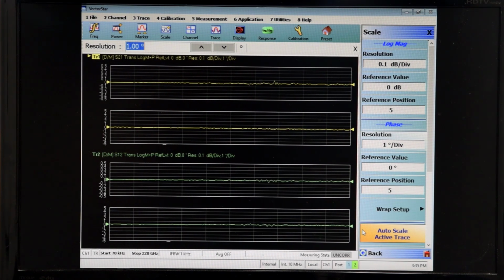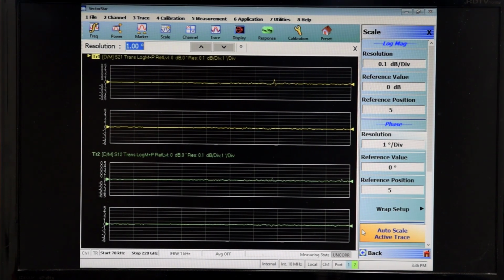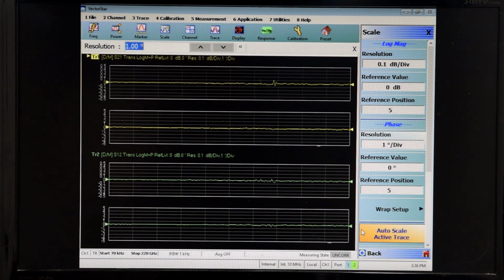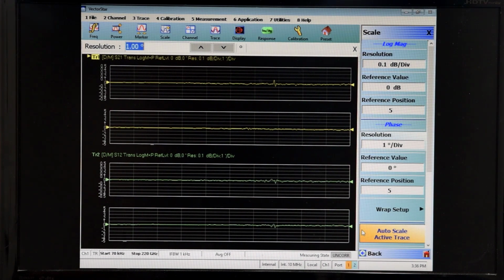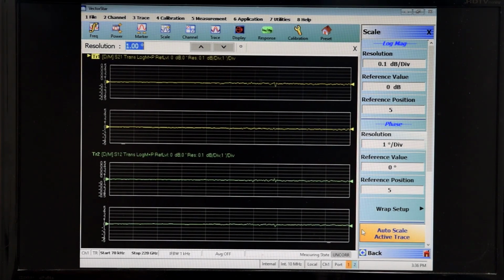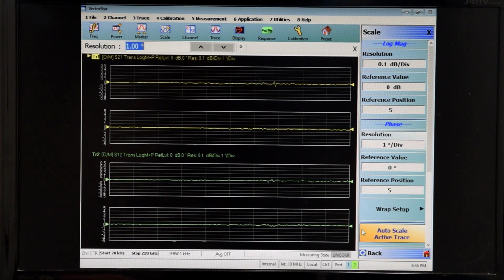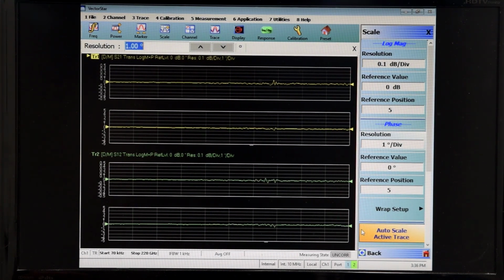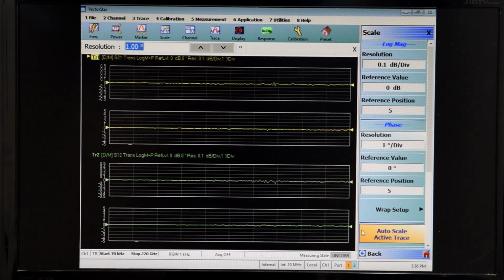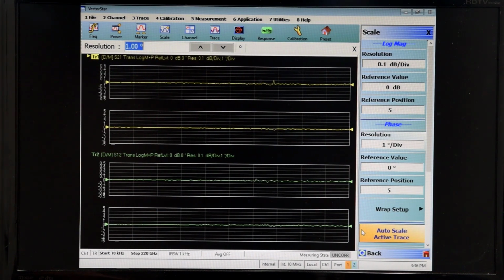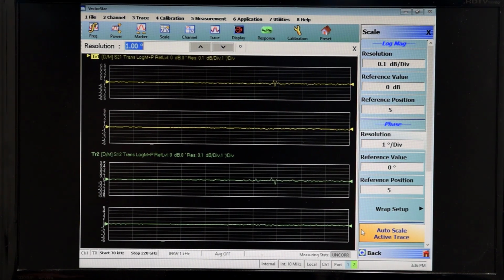So keep in mind that we are evaluating this system now because of that through adapter over the complete range from 70 kilohertz to 220 gigahertz, but without the probes attached, which gives us a good opportunity to evaluate the system without including any kind of drift that might be induced by the probes or the touchdowns. And so this will give us a good example of system performance and an opportunity to determine that the system is operating as we would expect. So then the next step would be to add the probes to this system and touch down and then evaluate over time and temperature as well.